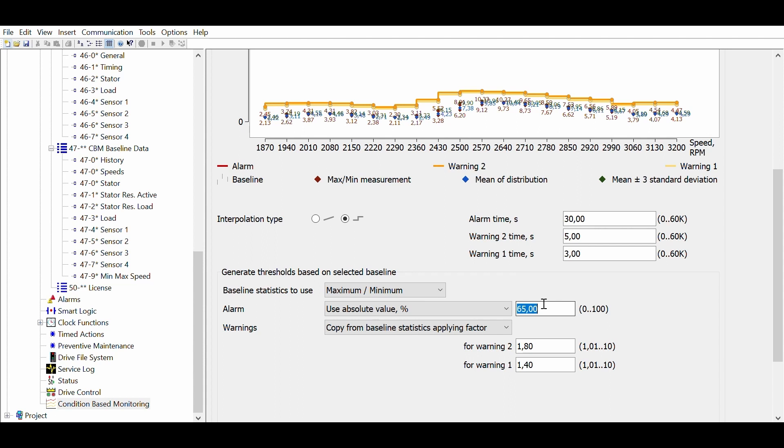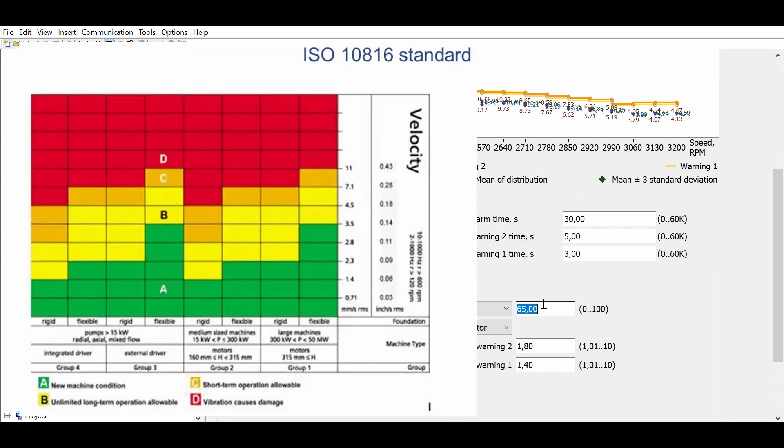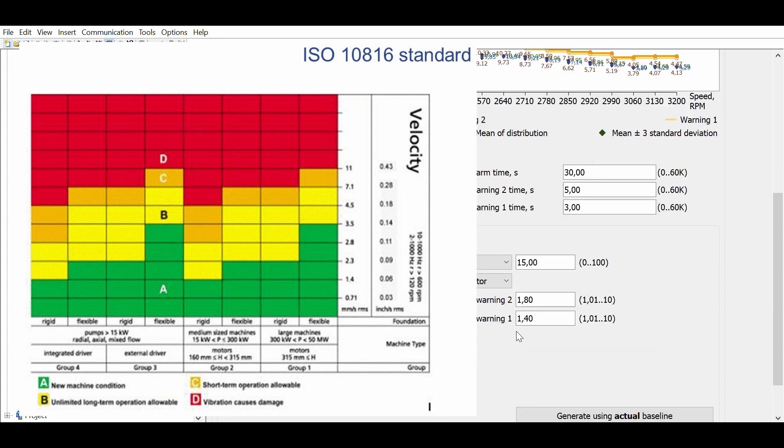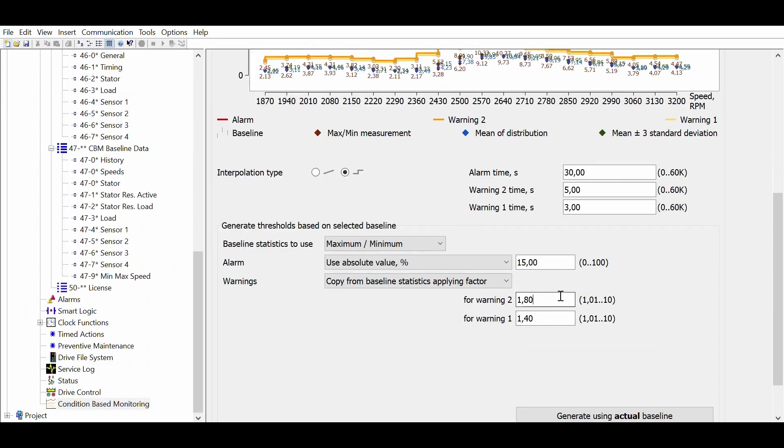For the alarm level we will use an absolute value. This can be, for example, a value recommended by the ISO 10816 standard. This is the absolute limit of vibration which is considered acceptable in this application. The thresholds will be a factor of the baseline.